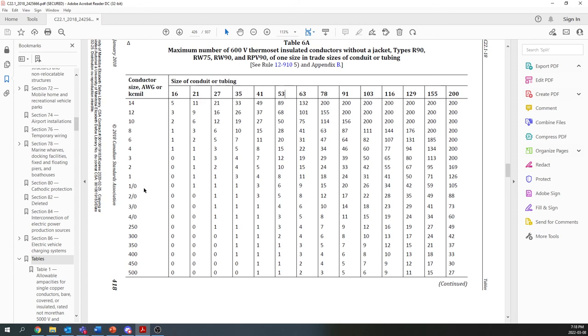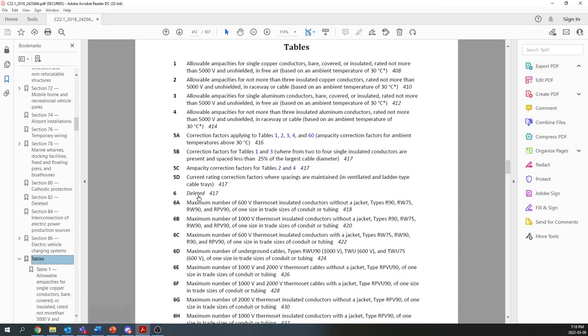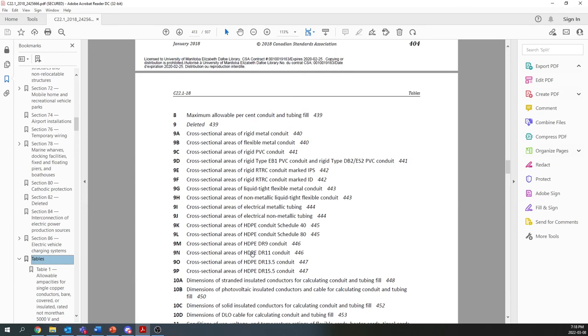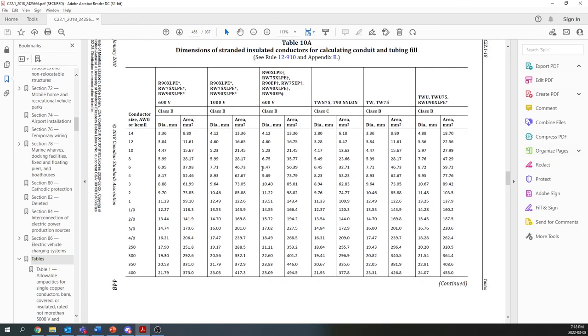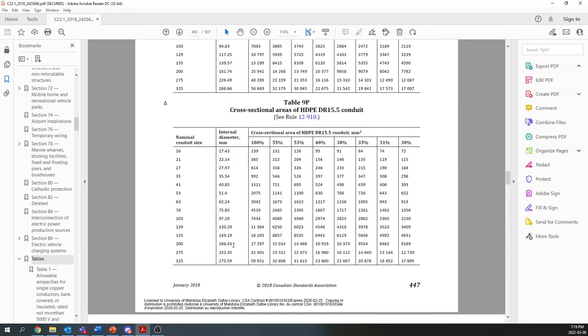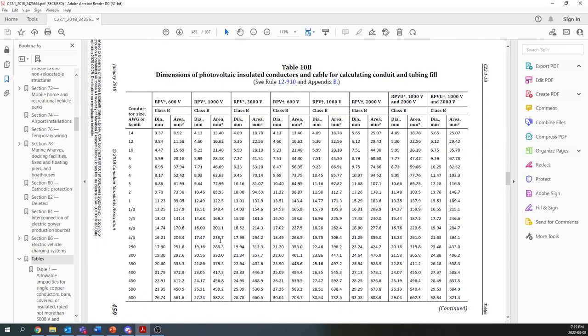But this may be a case where we want to calculate the conduit size. So what we would have to do in that case is go down to the cross-sectional areas of the stranded insulated conductors, Table 10A here, RW90 XLPE for 600 volts. I'm not going to do the calculation here, but I suppose I could. We're going to assume an insulated ground conductor. So 73.85 times 4, including the ground conductor, plus we have two number 4s, 52.46, and this is in millimeters squared, times 2. 400.32 is the number there that we have to go through.